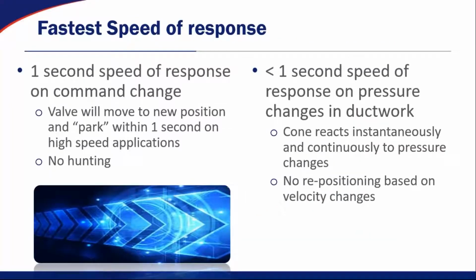When it comes to the speed of response on the Phoenix valves, there's really two parts to this. The first is the speed of response to command change. So in a wet chemistry environment, a high-speed environment, what's important is making sure that your valves track exactly what's going on in the room. So if you think about using a fume hood in a wet chemistry lab, you basically want the valve to move as fast as the sash can.